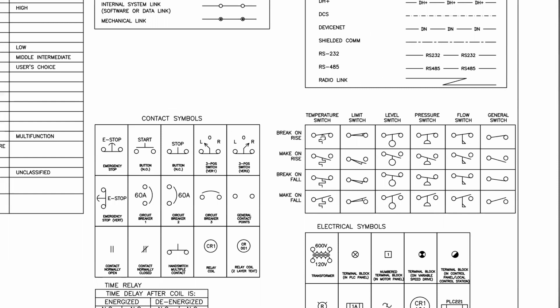Off to the side here, you'll have different switches. You've got temperature switches, limit switches, level switches, pressure switches, flow switches, and then generic switches. And they'll show here, you've got a break on temperature rise, you've got a make on temperature rise, you've got your normally open, your normally closed, depending on which direction you're looking to measure your temperature change in, your flow change, your pressure change. So if you have a bunch of different types of switches, it might be important for you to make sure you specify which ones you're using for the different processes inside of your drawings.